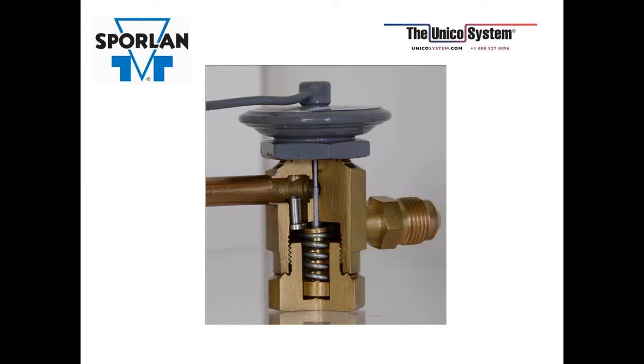It'll push the poppet closed, it'll force it through the pin and port, and then the expansion will occur, feeding the evaporator. In reverse flow, the liquid will come in from the right towards the left. It'll take the path of least resistance, so it won't go through the pin and port, because instead it's going to open up that poppet and allow free flow through the check valve.